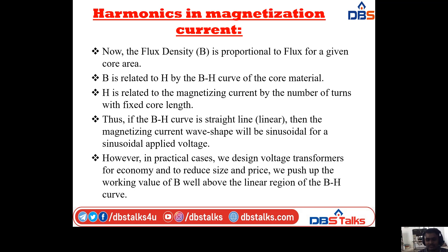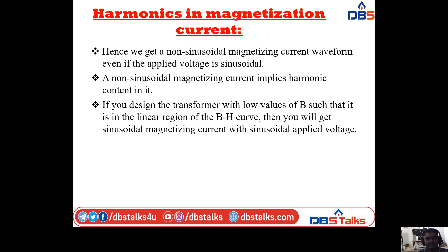However, in practical cases, we design voltage transformers for economy and to reduce size and cost, and we push the working value of B above the linear region of the BH curve. Hence we get a non-sinusoidal magnetizing current waveform even if the applied voltage is sinusoidal. A non-sinusoidal magnetizing current implies harmonic content in it.